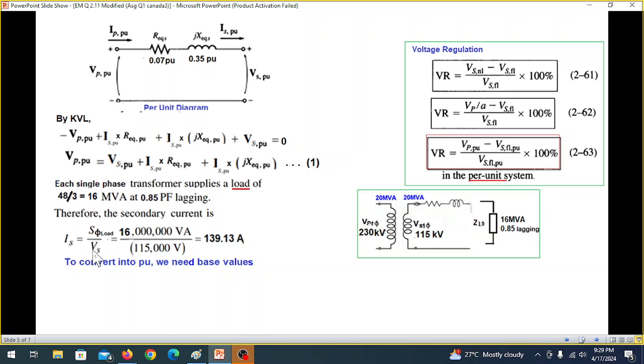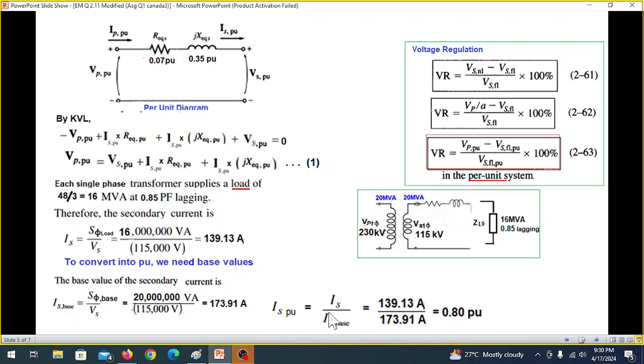Now, for base current, formula remains same, except that we are now calculating here. Therefore, S load will not be 16 MVA, rather it will be the rated MVA, 20 MVA. So the base value of the secondary current is S phi base over VS, so it is 20 MVA from here, divided by the same voltage, so it is 173.91 Ampere. Now that we have got the base current and the actual current, we can find the PU value. So ISN per unit is IS actual divided by base, from here, 139.13 over base, that is 0.80 per unit.